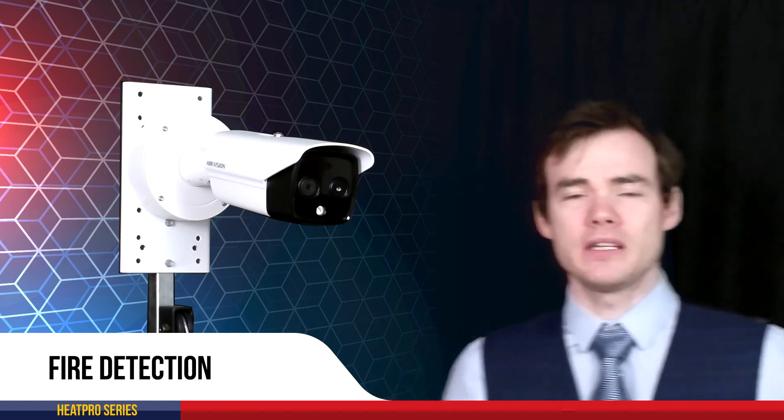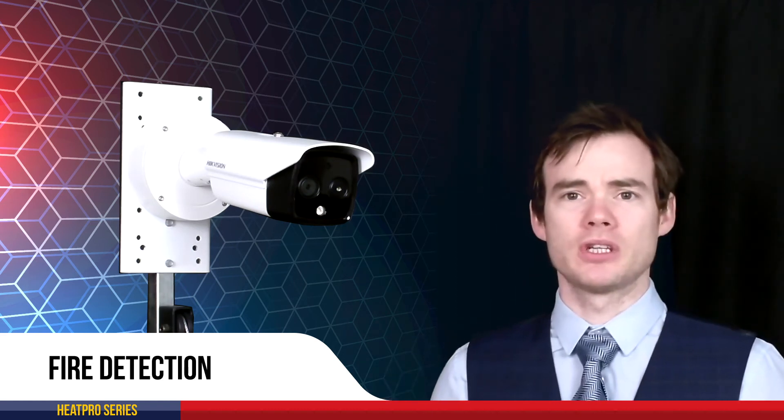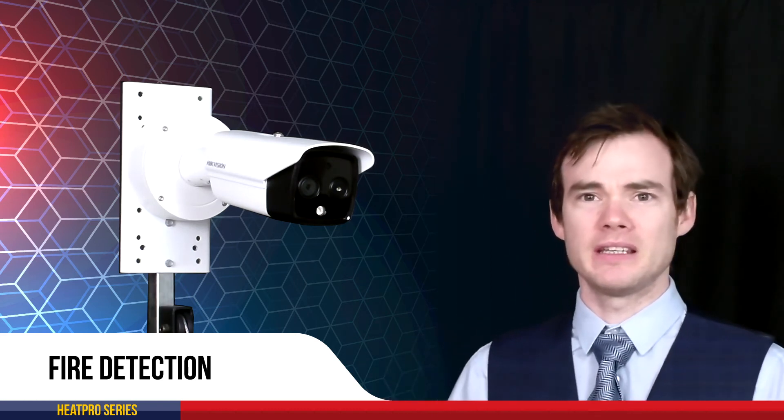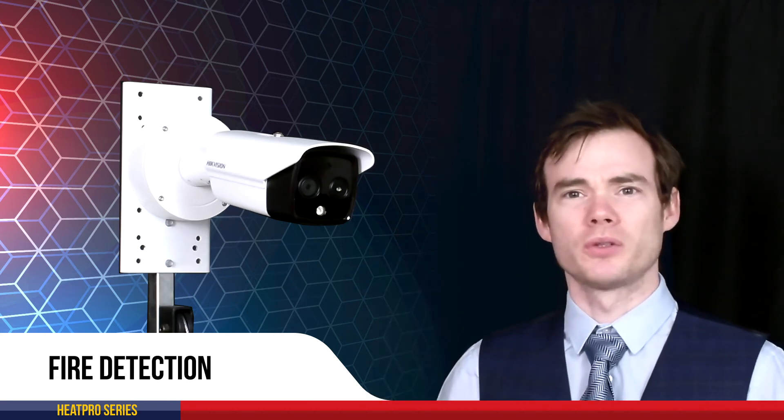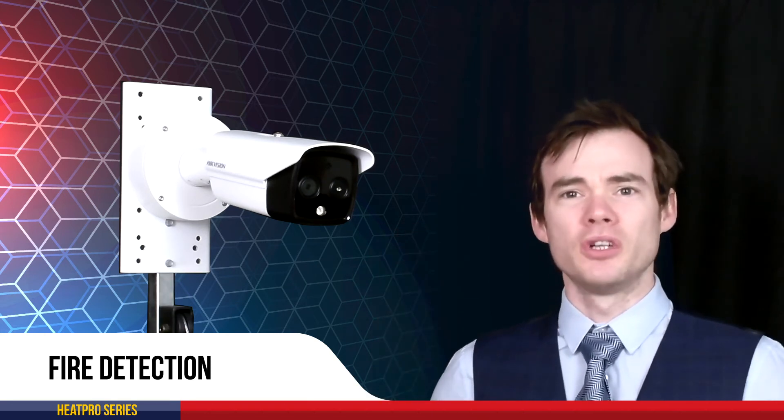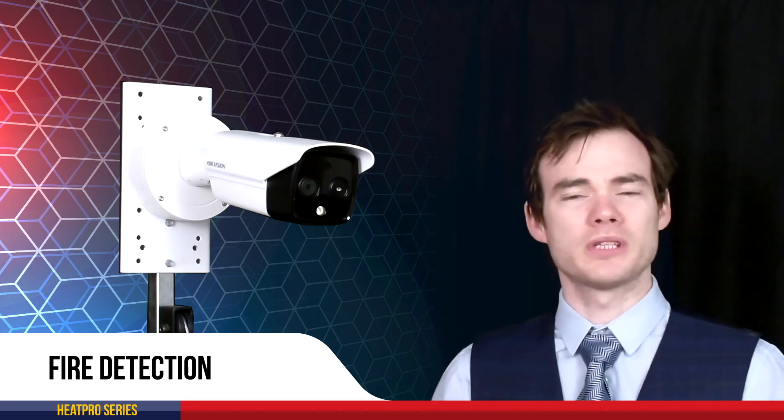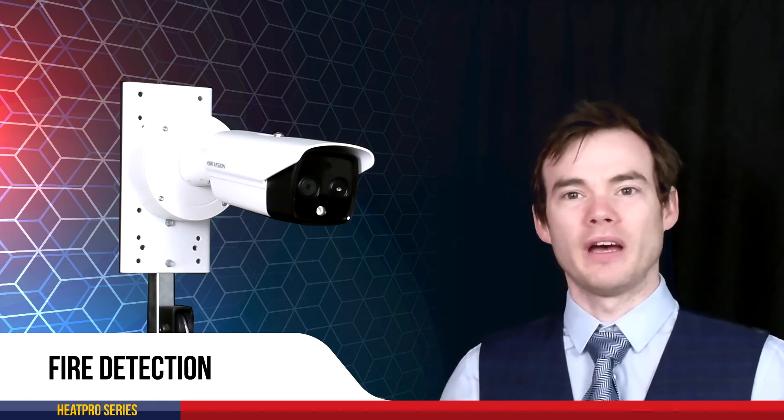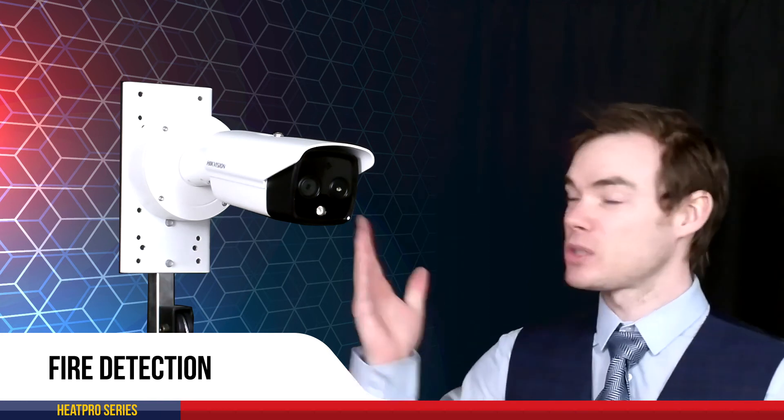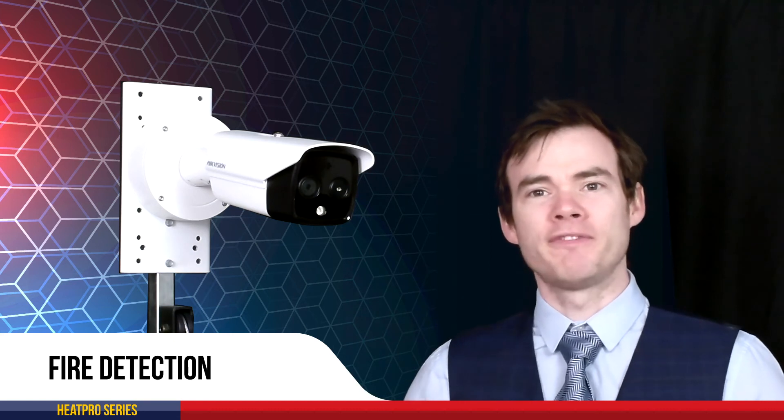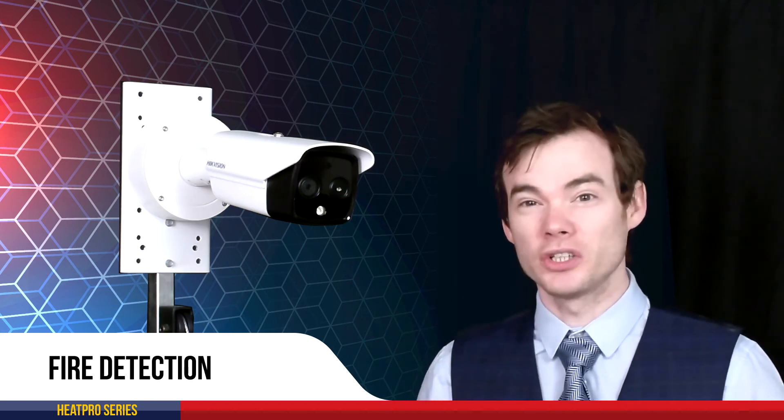Now we would never say remove your smoke detectors and your fire detectors from the scene. This is not to replace those sort of things. Smoke detectors and fire alarms do save life and limb. However, the downside of those is they only activate upon a fire actually being commenced. In this one, because we can do the temperature measurement side of things, we can get the system to alarm before the fire has actually occurred.